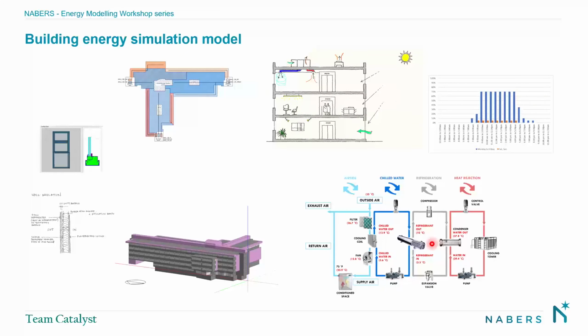In the process of making chilled water, there's work being done by the compressor, and so the chiller gets warm. That needs to be cooled to keep it operating efficiently. So all of the heat that is pulled out of the zone, plus what's picked up because of inefficiencies in the system, is dumped into the condenser vessel.